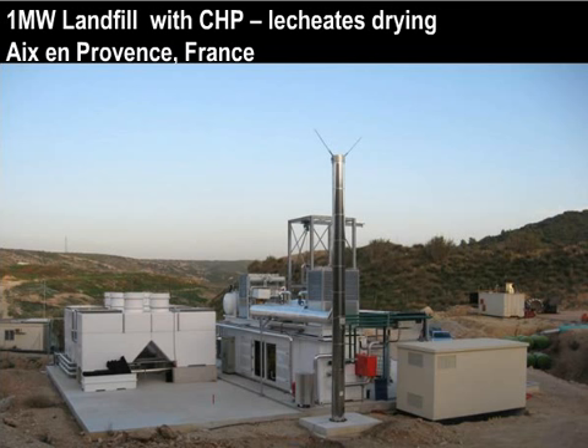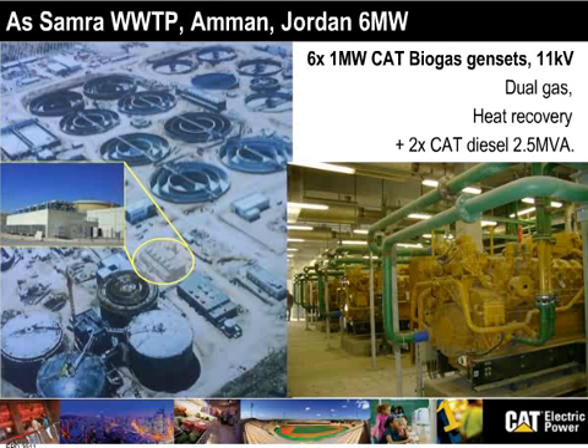Another one extremely popular and required combined heat and power are on the wastewater treatment plant. Wastewater treatment plants use anaerobic digesters to digest the wastewater waste. And here is an example in Jordan, 6 megawatt, where the heat of the genset will actually be fed to the digester, enhancing and quickening the digestion process of the wastewater treatment plant.